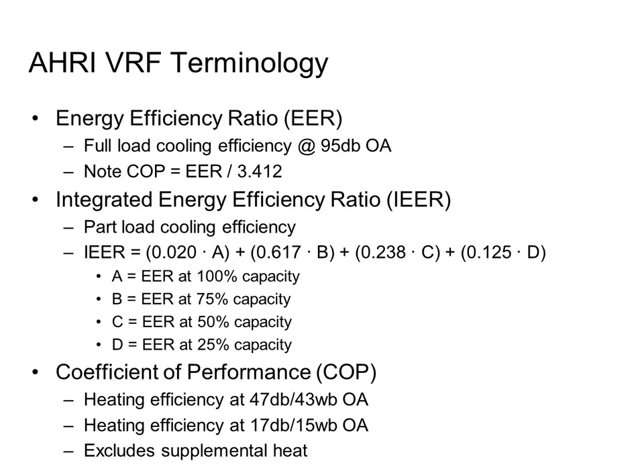One thing to note on this heating discussion is that the COP of the heating is the COP of the heat pump heating. If you've chosen to use electric backup supplementary heat or a boiler or something like that for supplementary heat on a really cold day, like Robert was asking about earlier, that energy is not included in the discussion. So really this is the COP, assuming you don't need any backup heat at that moment.